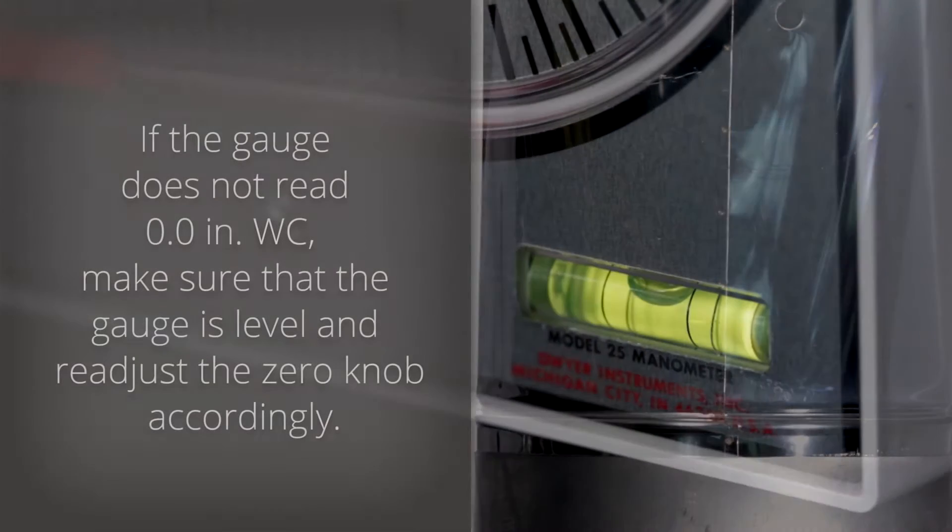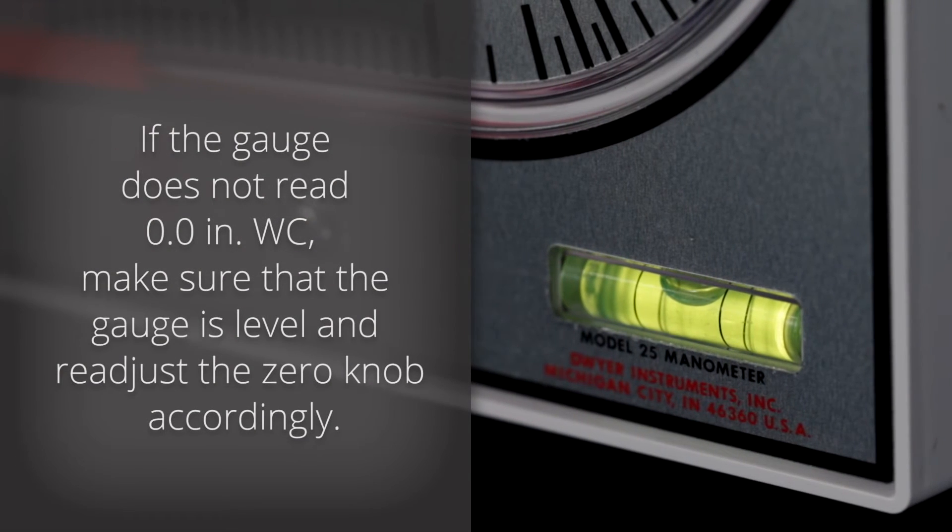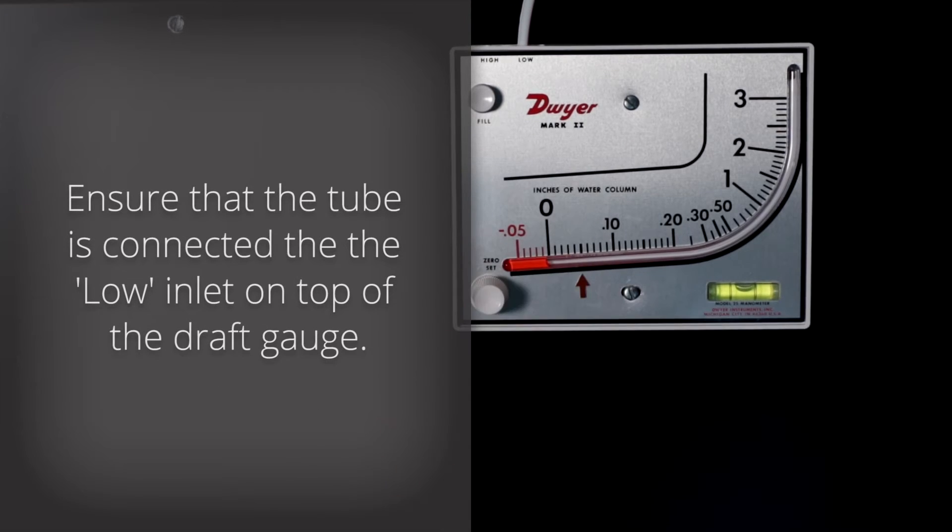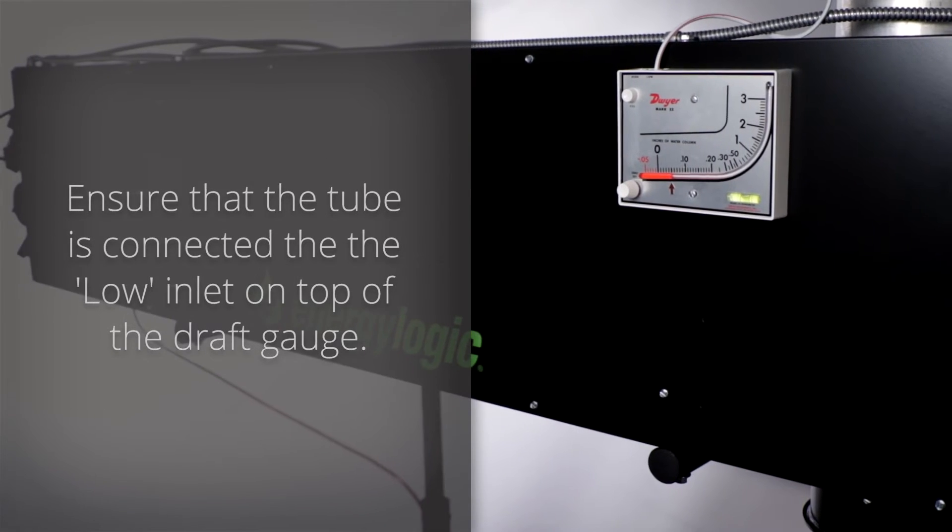If the gauge does not read 0.0 inches of water column, make sure that the draft gauge is level and readjust the zero knob accordingly. Ensure that the tube is connected to the low inlet on top of the draft gauge.